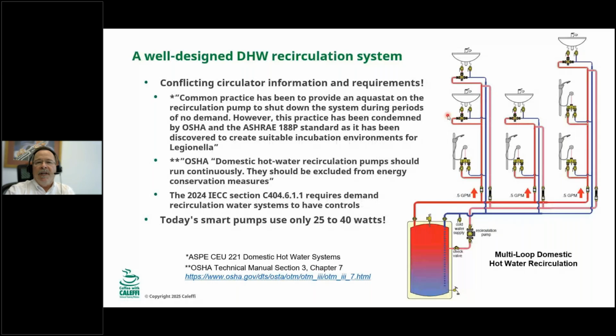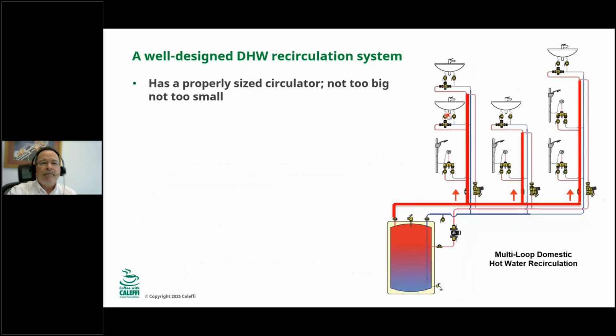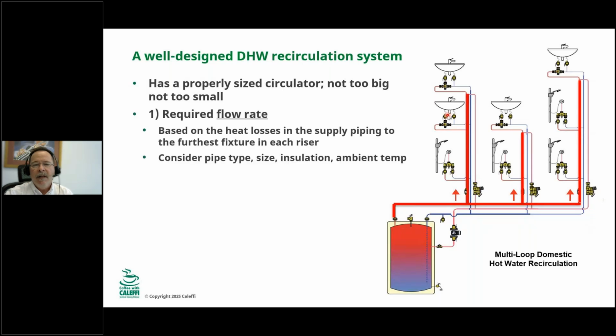Okay, sizing the circulator. Let's talk about sizing the circulator. There's two steps. The first step in figuring out which circulator you need is to calculate your flow rate. And the way we do that, let me go ahead and go down here. To calculate the flow rate, you use this equation here: GPM equals BTUs per hour over 500 times delta T.